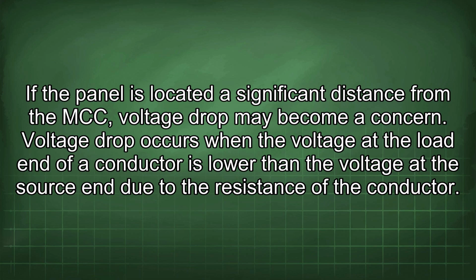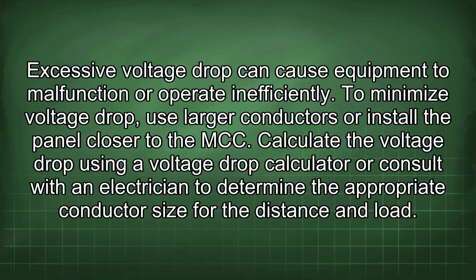Voltage drop occurs when the voltage at the load end of a conductor is lower than the voltage at the source end due to the resistance of the conductor. Excessive voltage drop can cause equipment to malfunction or operate inefficiently. To minimize voltage drop, use larger conductors or install the panel closer to the MCC. Calculate the voltage drop using a voltage drop calculator or consult with an electrician to determine the appropriate conductor size for the distance and load.